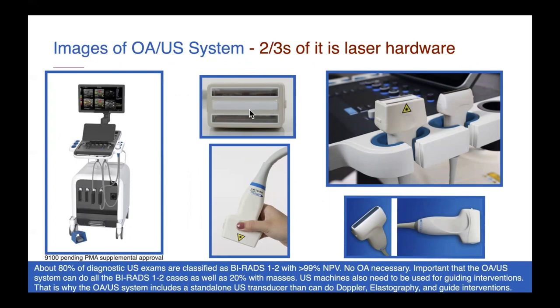The ultrasound transducer is in the center. It's an 18 megahertz transducer. These are quartz laser windows out of either side, and we send both wavelengths out of both sides. This is the side view of the duplex probe. The thicker cord contains a combination of laser fiber optics and the electronics for the ultrasound probe.